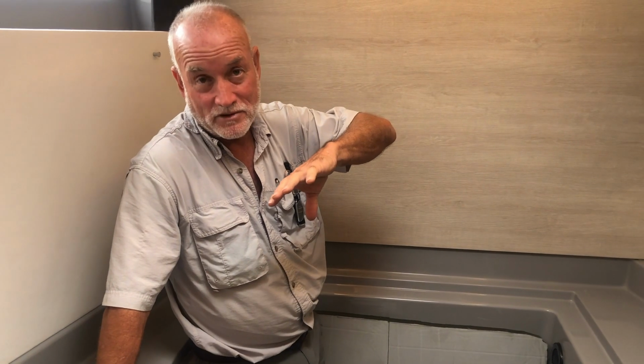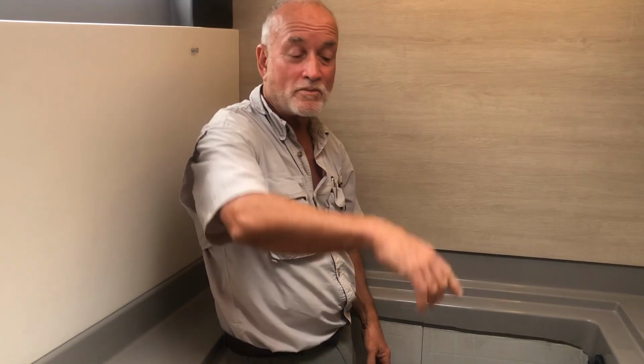Turn the power off when you pickle it. When you turn the power back on, it's going to assume, well, I don't know if I've been off for a minute or a year, so I'm assuming it's been pickled, and it's going to tell you, has the system been stored? You're going to say yes, and then it will go through its own unpickling process. It will tell you right on the control panel. We're flushing, open pressure relief valve, flushing for 20 minutes, purging storage solution.